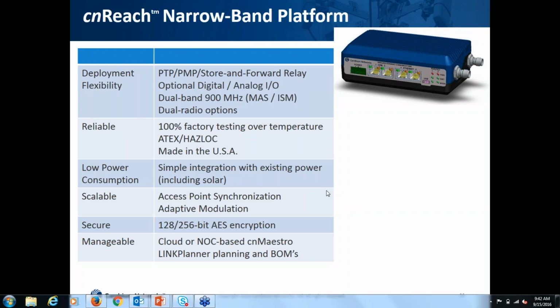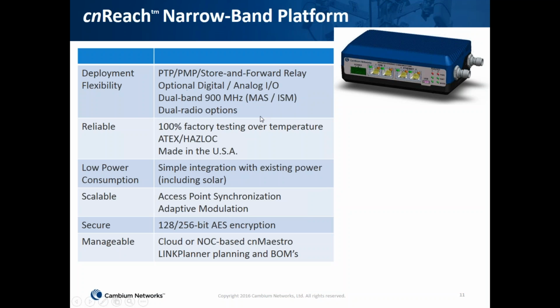How many digital analog I/O are supported? I don't have all the detail in this presentation. There's certainly more available. There are 8 different pins, and they're programmable in how they're suited for either input or output, and whether I'm measuring a voltage level, a current, or a count. So I can do quite a lot of flexibility with that, and that's all then readable using traditional Modbus type of application. So I can read the status of those digital analog I/O using Modbus protocols.